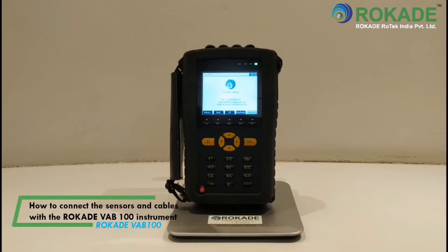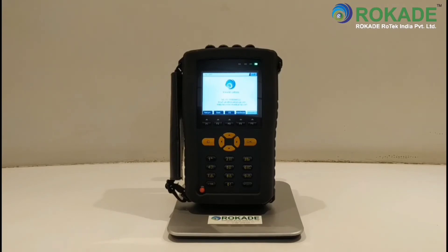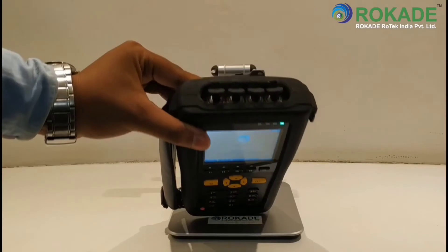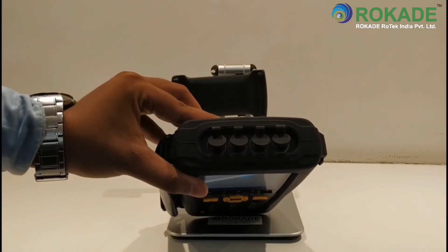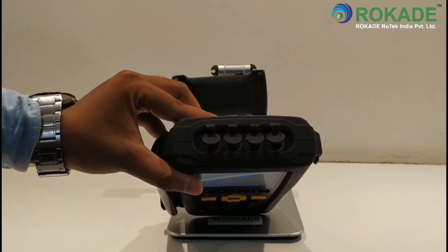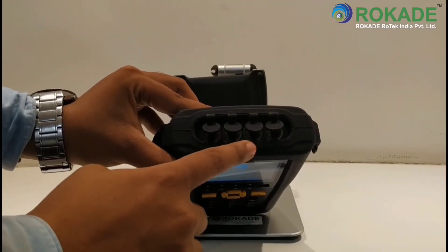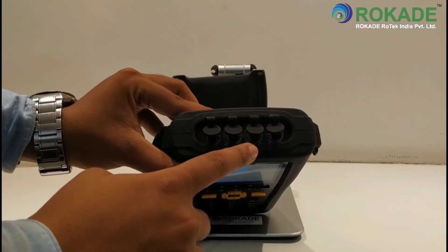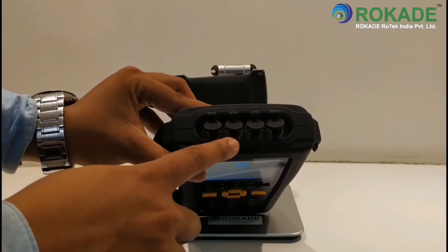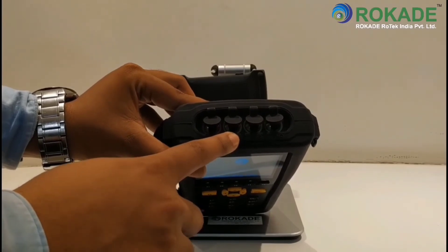How to connect the sensors and cables with the ROKADE VAB100 instrument. There are four LEMO connection ports on the top of the instrument. The first and second green color ports are used as channel 1 and channel 2 for accelerometer sensor connections. The third yellow color port is for connecting the RPM sensor.